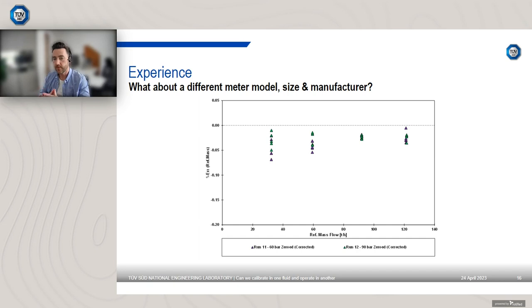So previously you can see that we had calibrated the device at 5, 10, 20, 40 and 80 bar. We then derived that pressure compensation factor. I've now operated at 60 bar and 90 bar, and you can see these are two pressures that we didn't calibrate at, but using that pressure compensation factor, you can see that we've got the meter well within the 0.1% specification. Now remember, the meter was slightly out of specification. It was underreading by 0.03%, hence that term that I showed you. So it's not perfect, but the pressure compensation factor is very, very good.